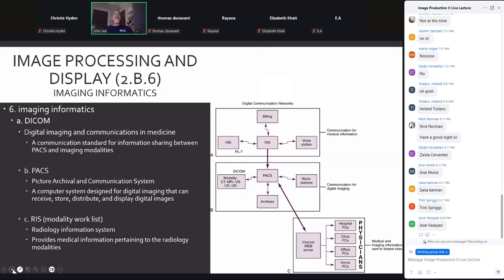For informatics, DICOM, Digital Imaging and Communications in Medicine, is a protocol required for all image acquisition. CT, CR, DR, fluoro, MR, ultrasound, all of the modalities: in order for those digital images to go into PACS, there has to be a DICOM to communicate with those systems and PACS. Every manufacturer's got their own. We can't just use one for all of them. So DICOM is the communication standard for digital imaging.